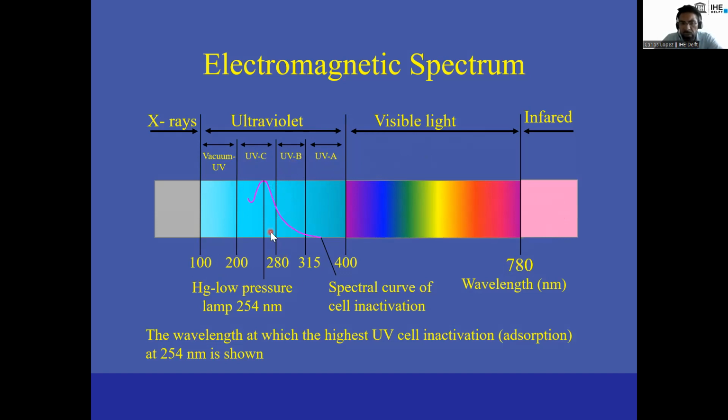with different levels of UV, like UVA or UVB. The strongest disinfectant level is provided by UVB, and this is a bit lower. Sorry, it's UVC. It's at 254 nanometers, and this is the UV light that has the strongest inactivation, the UVC. Solar light has a combination of different levels. Sunlight can have mostly UVA or UVB, but the most effective is UVC with this level.